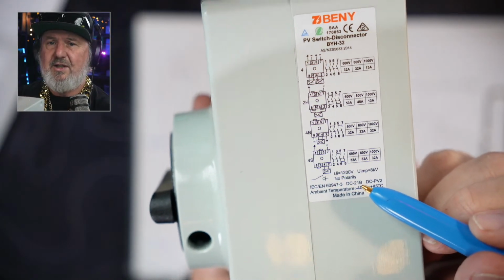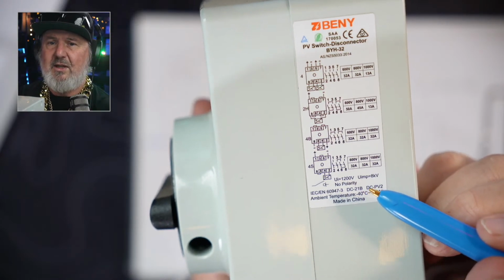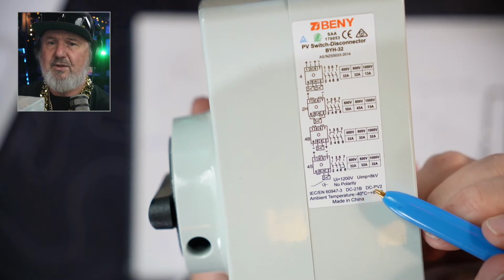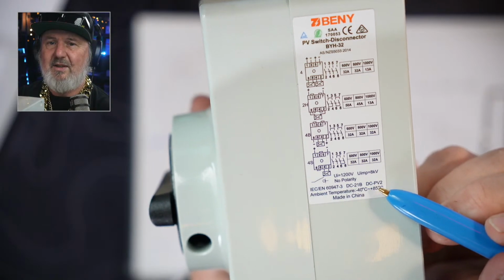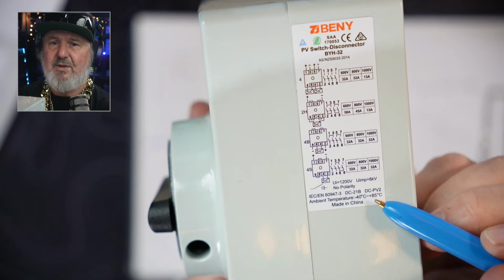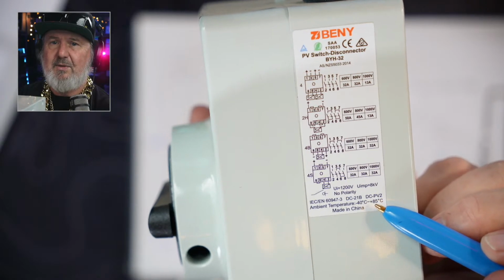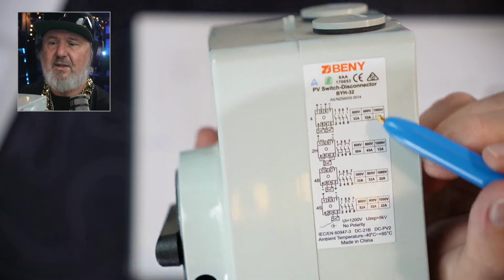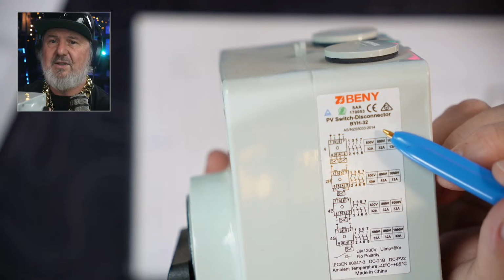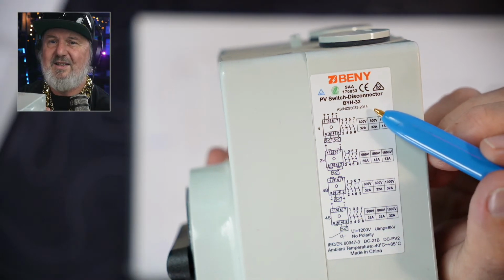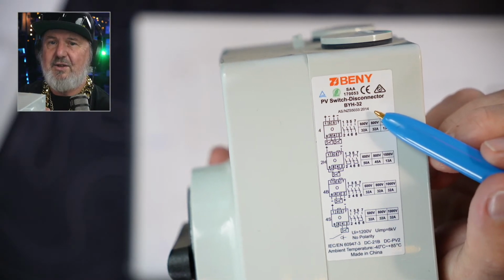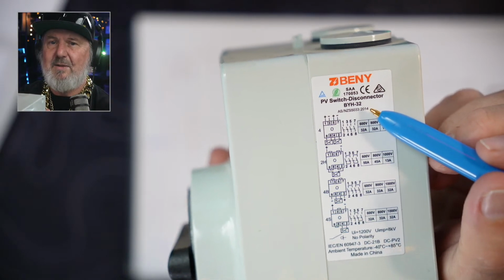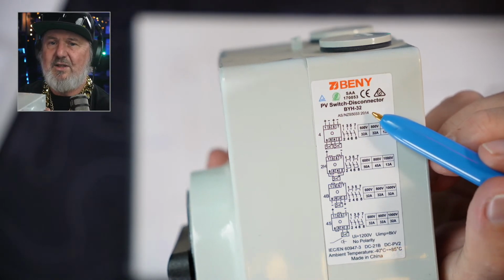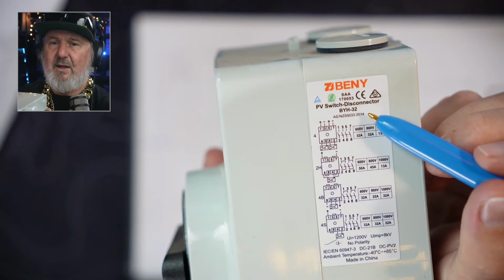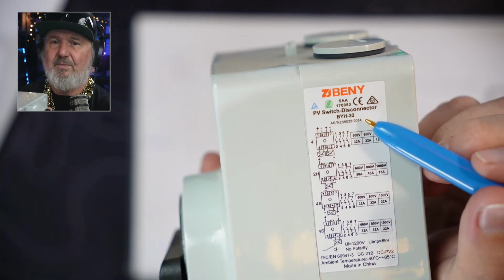utilization category. There's DC21B, which in the latest version of the standard is now called DCPV2, which is operate at least once every 30 seconds. So there's quite a bit of useful information just written on the side there. They even list compliance to the old 2014 standard. So this is an old DC isolator I've had on the shelf for a while. They've probably updated this to show it's compliant to the 2021 edition for iMake, iBreak, and iThermal. So there you go.